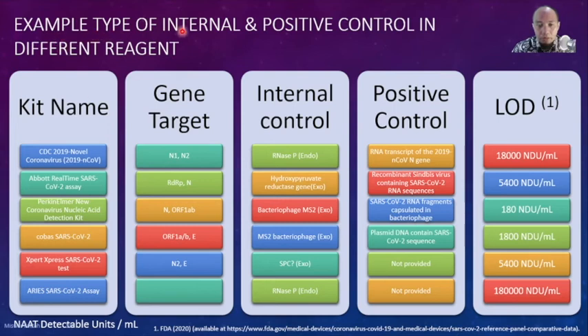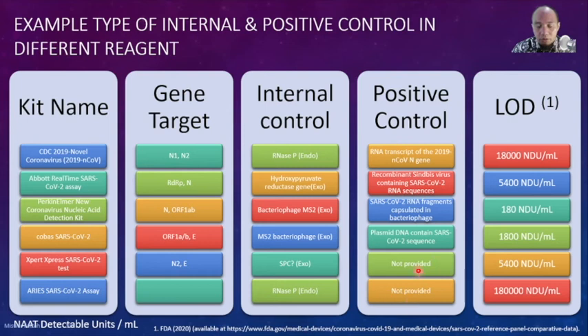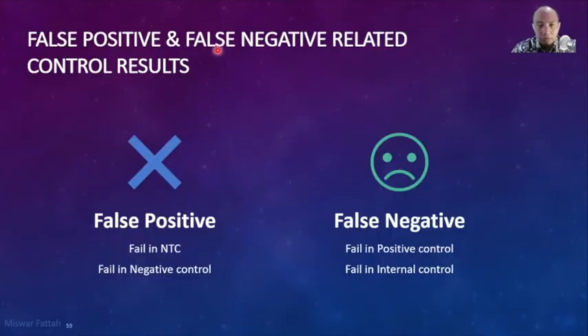Examples of internal control and positive control in different reagents: CDC uses RNase P (endogenous), and Aries from Luminex also uses endogenous. Most other reagents utilize exogenous controls. This type of control does not monitor the sampling phase. For cartridge-based systems, positive control is often not included in the kit. False positive can be monitored from failures in no-template control and negative control. False negative is indicated by failures in positive control or internal control.